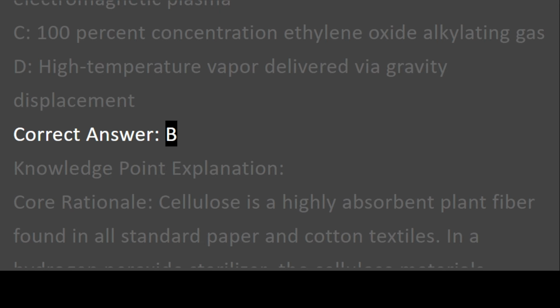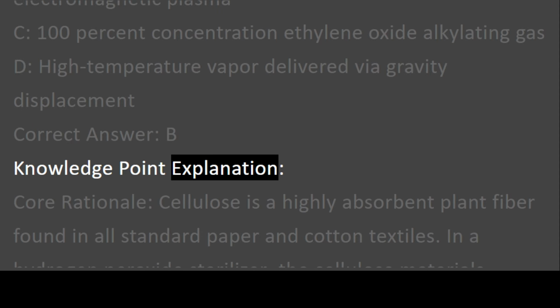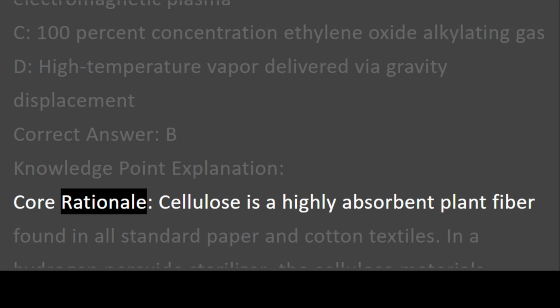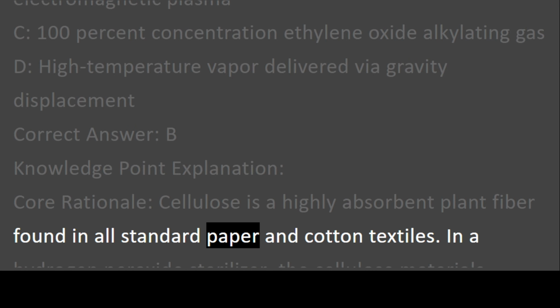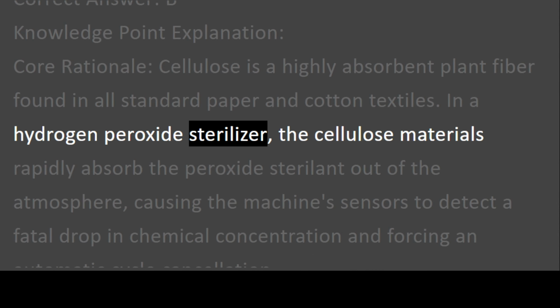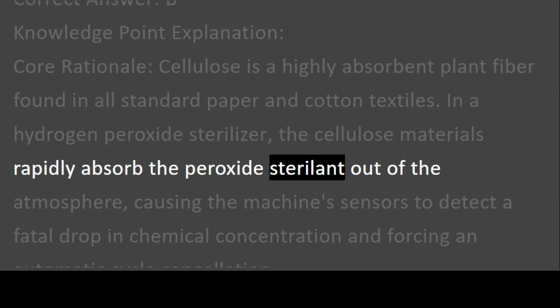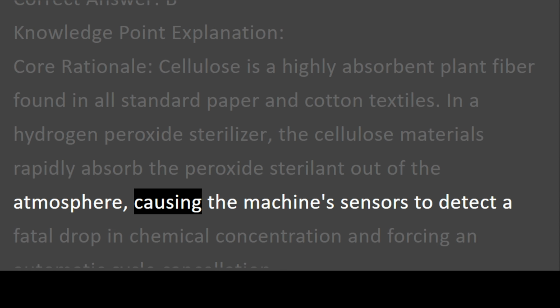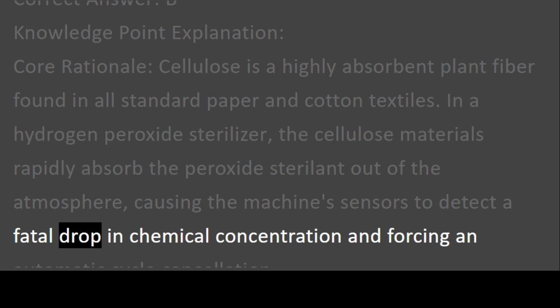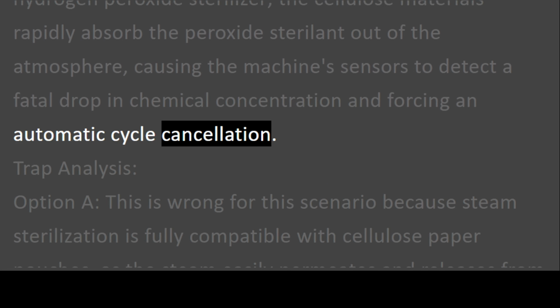Correct answer, B. Knowledge point explanation. Core rationale. Cellulose is a highly absorbent plant fiber found in all standard paper and cotton textiles. In a hydrogen peroxide sterilizer, the cellulose materials rapidly absorb the peroxide sterilant out of the atmosphere, causing the machine's sensors to detect a fatal drop in chemical concentration and forcing an automatic cycle cancellation.